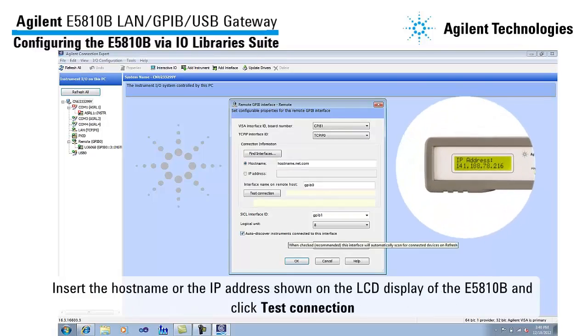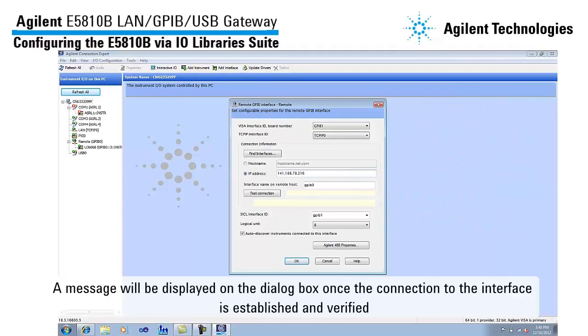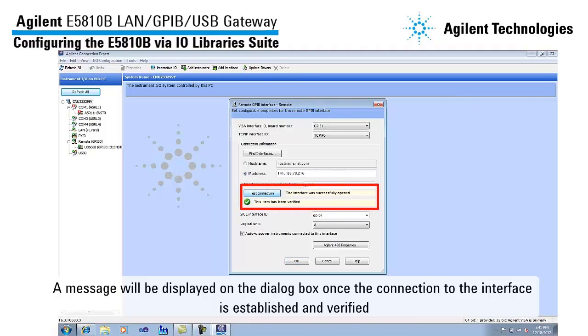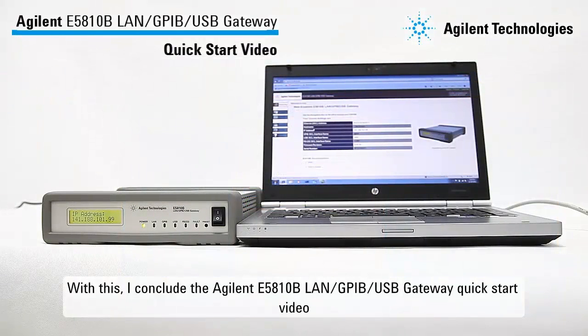Insert the hostname or IP address shown on the LCD display of the E5810B and click Test Connection. A message will be displayed on the dialog box once the connection of the interface is established and verified. With this, I conclude the Agilent E5810B LAN GPIB USB Gateway Quick Start Video. For more information, please visit www.agilent.com/find/E5810B.